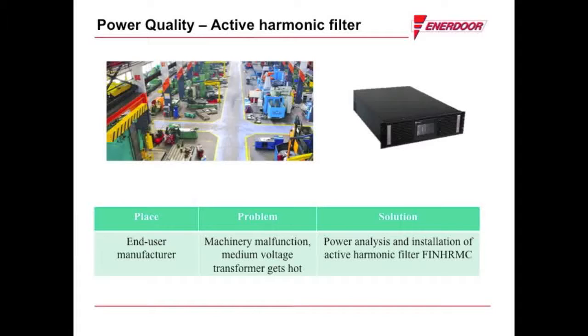Suspecting harmonic distortion to be the cause, Enerdoor suggested and performed a power quality analysis to confirm harmonic distortion was the culprit.